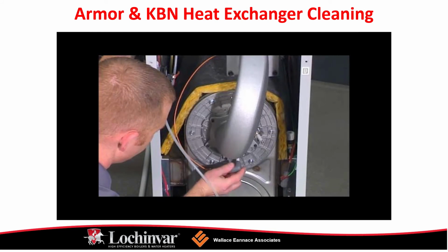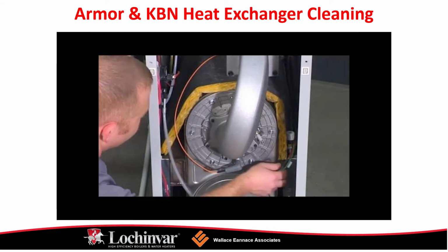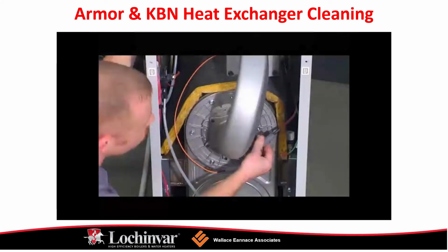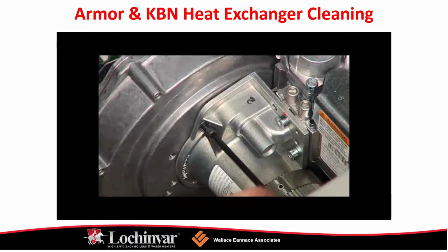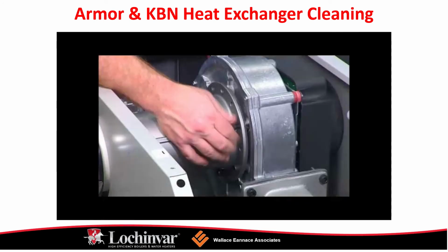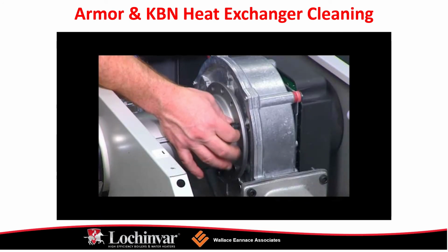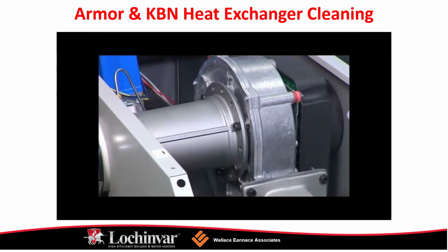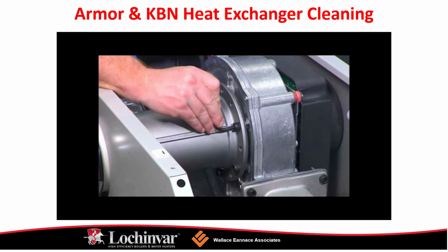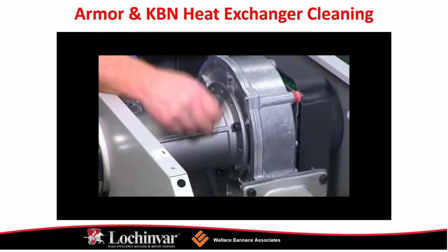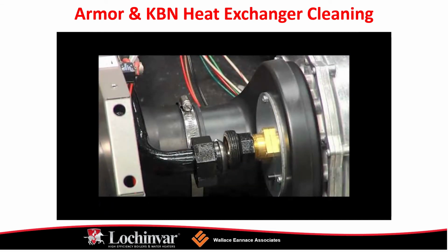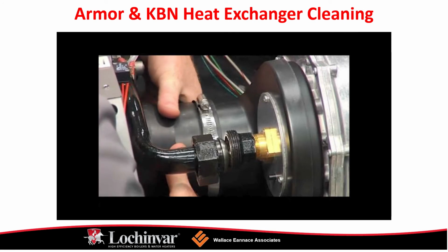Remove the wiring from the flame rod, spark igniter, and ground terminal from the front of the heat exchanger door. Using a 10mm socket or wrench, remove the nuts securing the heat exchanger door to the heat exchanger. Carefully remove the heat exchanger door with the blower and gas air arm still attached.